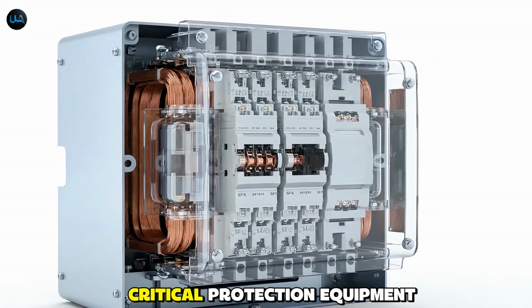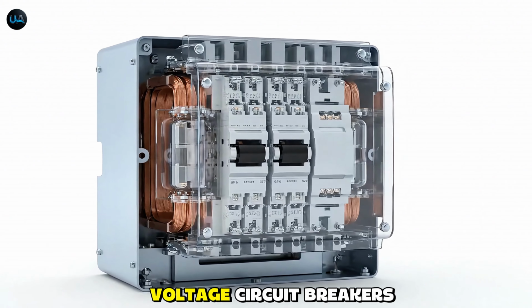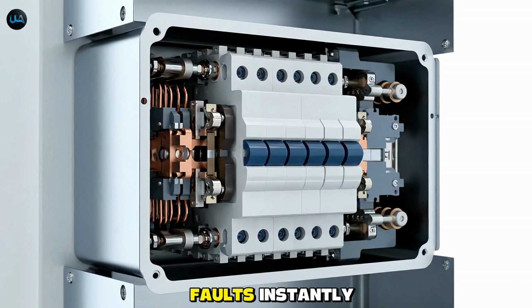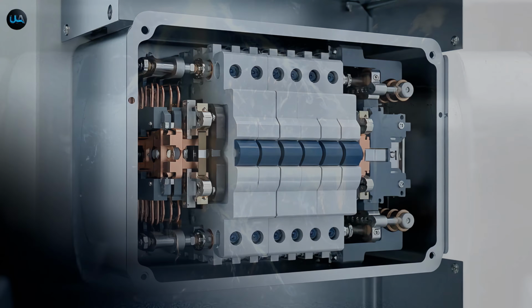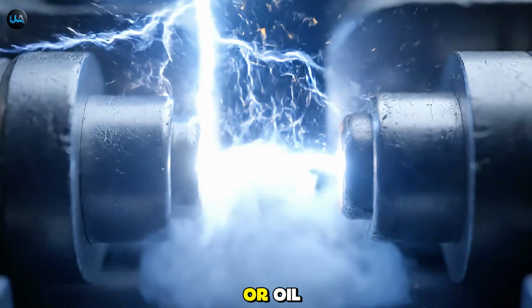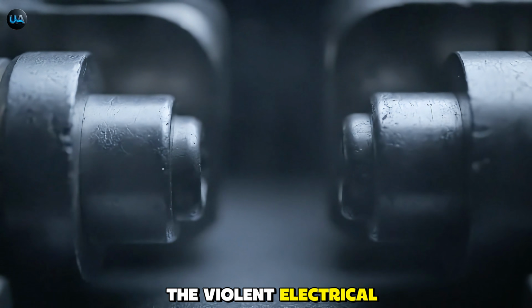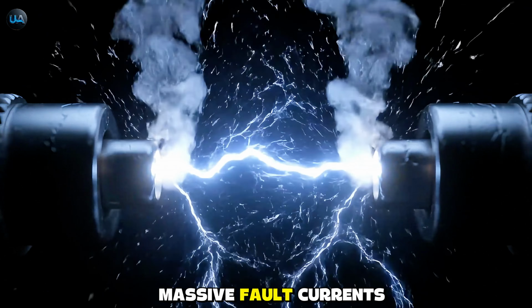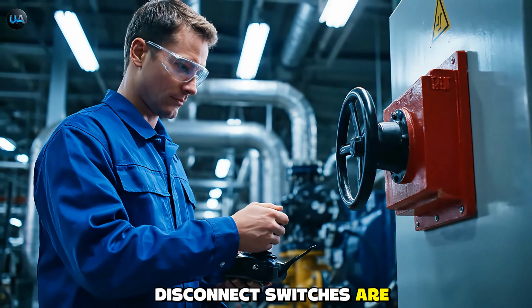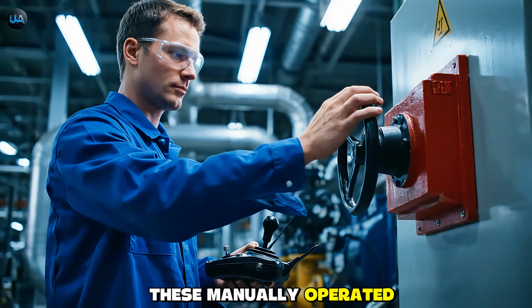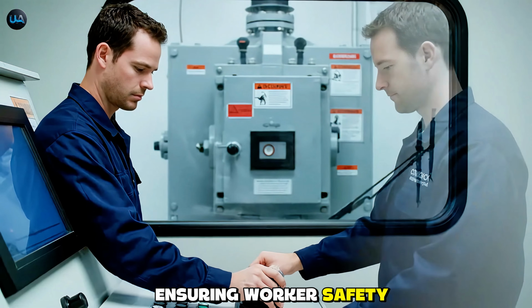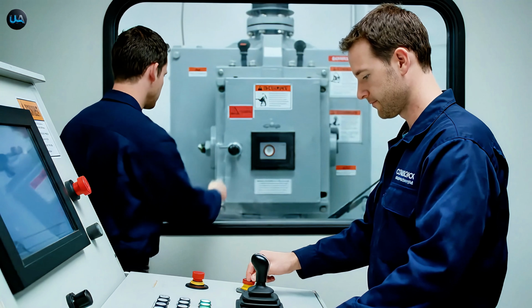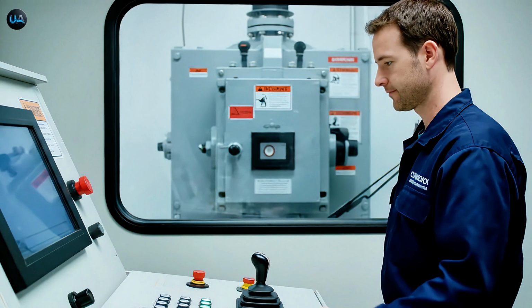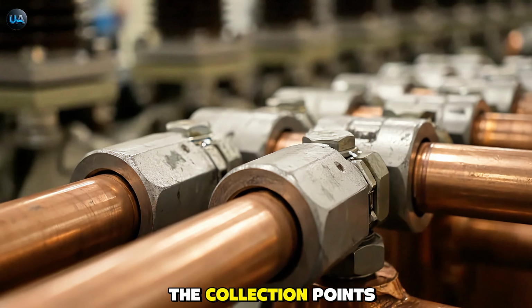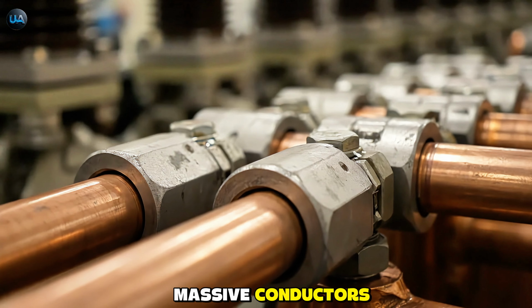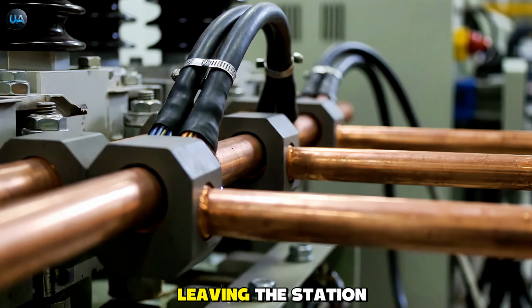Substations are filled with critical protection equipment, most notably high-voltage circuit breakers designed to isolate faults instantly. These specialized breakers use compressed gas or oil to rapidly extinguish the violent electrical arc formed when interrupting massive fault currents. Disconnect switches are used for maintenance. These manually operated switches isolate equipment, ensuring worker safety during repair or testing. Bus bars are the collection points within the substation, massive conductors that distribute power to different circuits leaving the station.